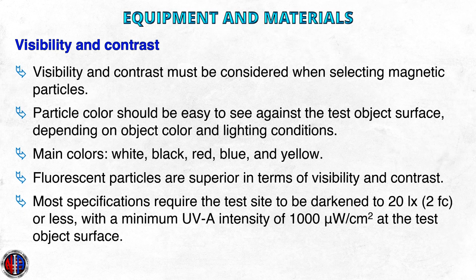Although fluorescent magnetic particles tend to be magnetically less sensitive than visible particles, they are far superior in terms of visibility and contrast, provided test lighting conditions are ideal. Most specifications require the test site to be darkened to 20 lux or 2-foot candle or less, with a minimum UVA intensity of 1000 microwatts per square centimeter at the test object surface. Proper test site darkening is crucial to gain the benefits of fluorescent particle application.